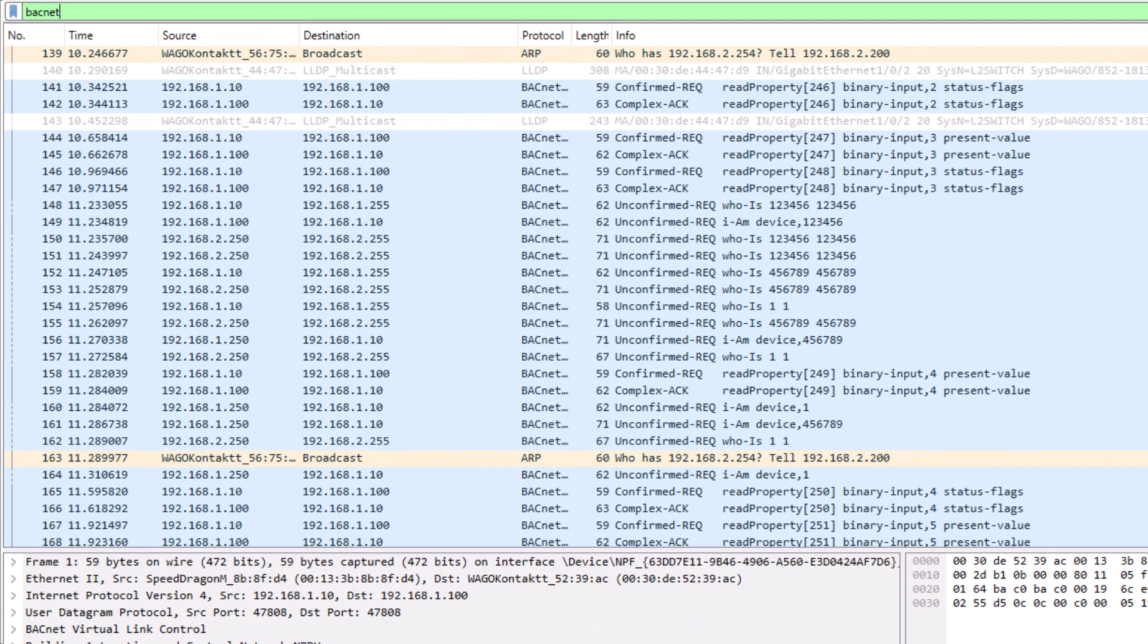We can analyze the network communication with Wireshark and see here how the BACnet broadcast telegram who is was sent and the reply as Unicast telegram I am was successfully received.